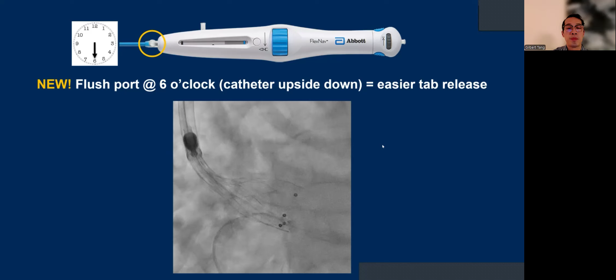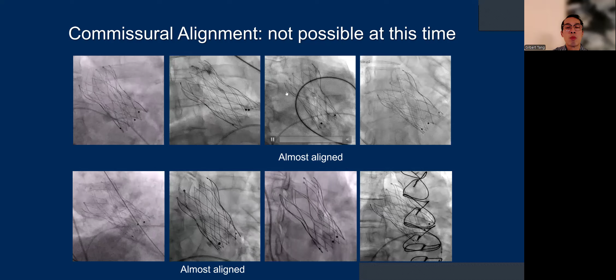Now, what about commissural alignment? So right now, the delivery system and the valve itself is not designed for active commissural alignment, and there's been no consistent technique to achieve that. And you can see that here, out of these 8 sample cases, only 2 are almost aligned on the cusp overlap view. However, coronary access, as you saw, is not a problem even with commissural misalignment. So the vision marker has perhaps been an aid to alignment in the future, because it might help pre-orient the valve in the descending aorta to track across the arch and to determine if the marker orientation is preserved.